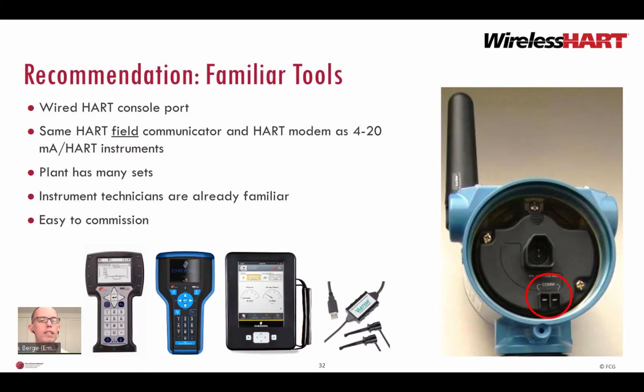WirelessHART solves this by using the same familiar HART field communicator or HART modem used for 4 to 20 milliamp instruments, which the plant already has, often many sets. Instrument technicians are already familiar with these HART tools. The result is sensors easy to commission with security credentials. Other wireless sensor network technologies cannot use these familiar tools.